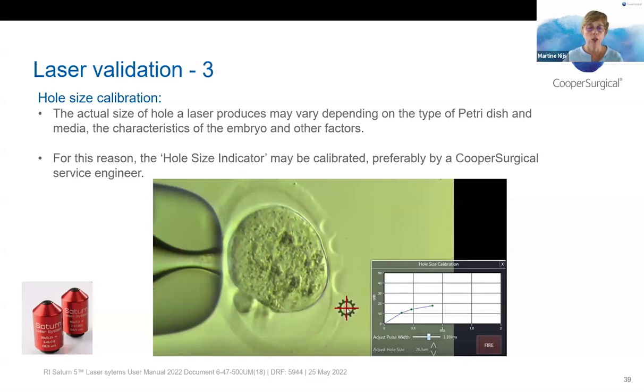principle. And so what they do is they use a zona pellucida of a non-fertilized oocyte. It needs to be fixed really at the level that you're doing your micromanipulation. You focus on the zona, and then you start lasering with 300 microseconds, for example, and then you can measure the hole that you have there. And then you go to 400, then you go to 800, etc., and you can have this graph as indicated here, the hole size calibration.